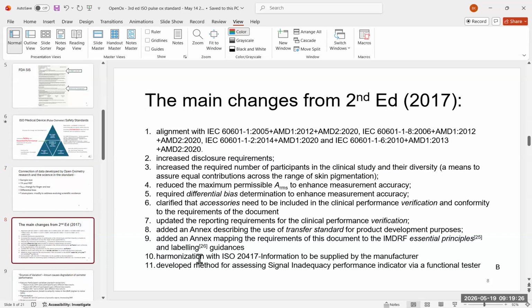Now, to that end, there are some main changes, 11 that we've identified. There are certainly more, but these are the main ones. And recognize it's not just improving what can be done from a SaO2 to SpO2 performance comparison, but as well to desktop or functional calibrator testing. So these functional testers are used for pulse rate. We're ignoring pulse rate in much of what we're saying, but recognize the pulse oximeter by the IEC and ISO standard are required to report just two variables. One is pulse rate, which again can be detected with a desktop type of testing device. And the other is SpO2, which has to meet a lot of other testing criteria, safety as well as performance.